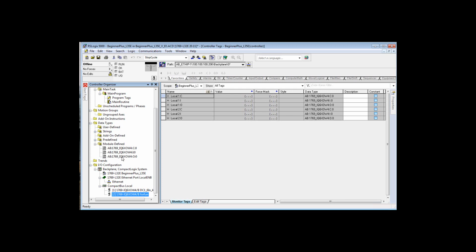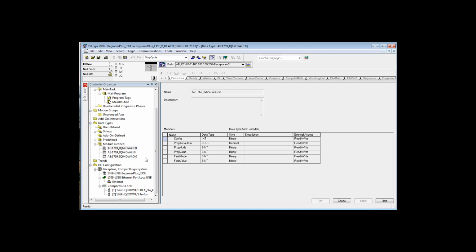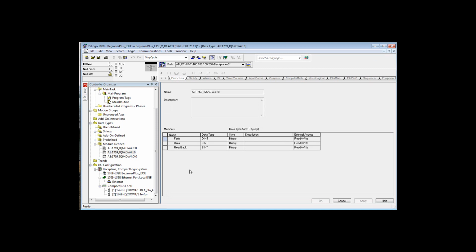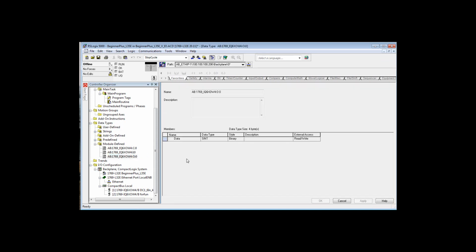If you want to call these the templates, but in proper data terminology, they're called a class of objects, of data objects. Each one of these has a data structure made up of atomic data types. We already looked at that one. You can see you've got an integer, a Boolean, and 4 single integers. Those would be 8-bit words. This one, we have a double integer and 2 single integers. And the last one, the outputs, we strictly have data. A single integer, 8 bits.